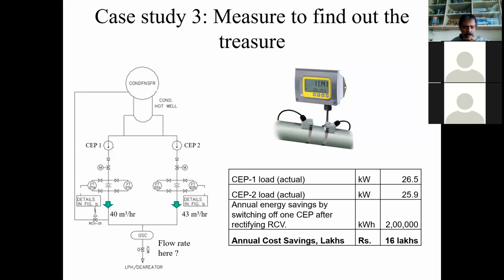And here, to our surprise, we found that both the pumps were operating. Normally, one pump is operating and one pump is a standby. In this case, both the pumps are operating. So we had an ultrasonic flow meter, and we measured at this point. As you measure, we find that this is 40 meter cube per hour. At this point, if you measure, it is 43 meter cube per hour. But when you put the measurement here, this shows only 40 meter cube per hour. 40 here, 43 here, you should have got 83, but you're getting only 40.